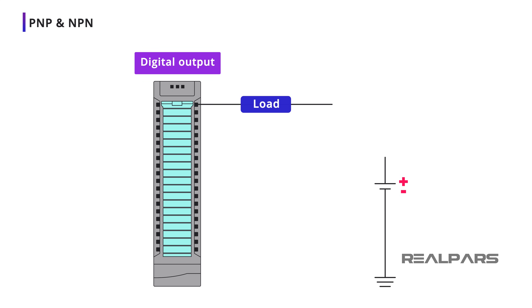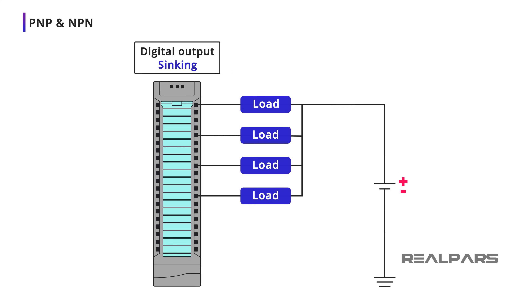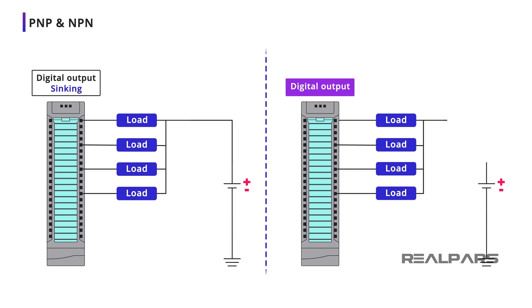You might ask: when looking at a wiring diagram, is there a quick way to identify if a module is sinking or sourcing? Here's something that might help you. Each module output used will connect directly to one terminal of a load. The other terminals of each load will be wired together. If the wired-together load terminals connect to the plus terminal of the power supply, you have a sinking module. If the wired-together load terminals connect to the negative terminal of the power supply, or ground, you have a sourcing module.